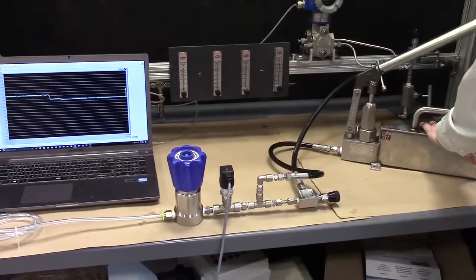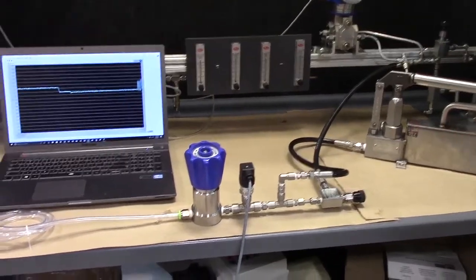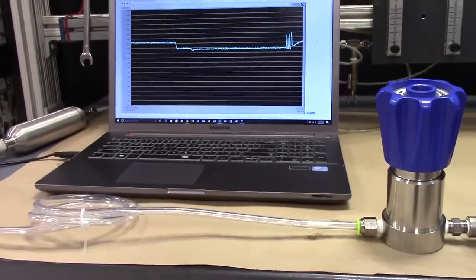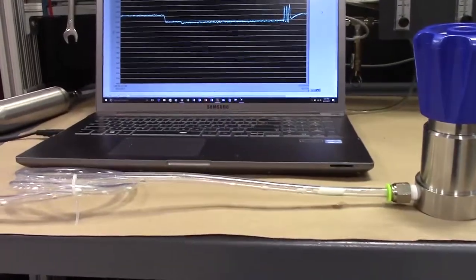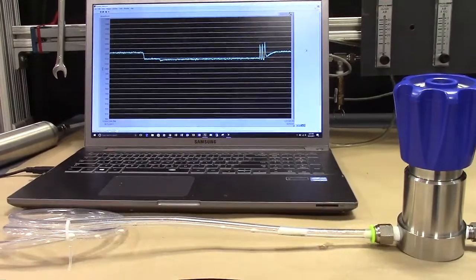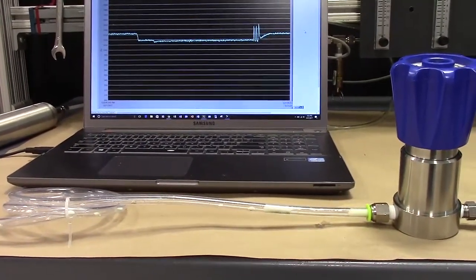So here we have about one liter a minute of nitrogen flow through the spring-loaded back pressure regulator. I've just introduced three pulses of liquid to the system which we see by those three characteristic spikes in the plot of pressure versus time.